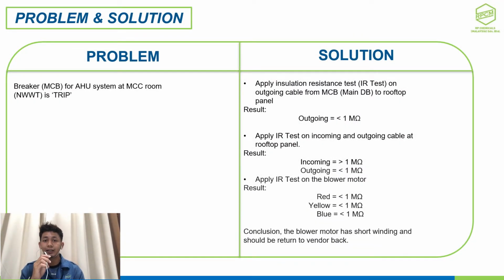Next part is the problem that occurred during my industrial training program and the solution that was proposed by me. The problem chosen by me is to troubleshoot a trip breaker for the AHU system at the MCC room, new wastewater treatment. Then I proposed my solution, which is to apply the insulation resistance test (IR test) to the outgoing cable from the main breaker using a megohmmeter.